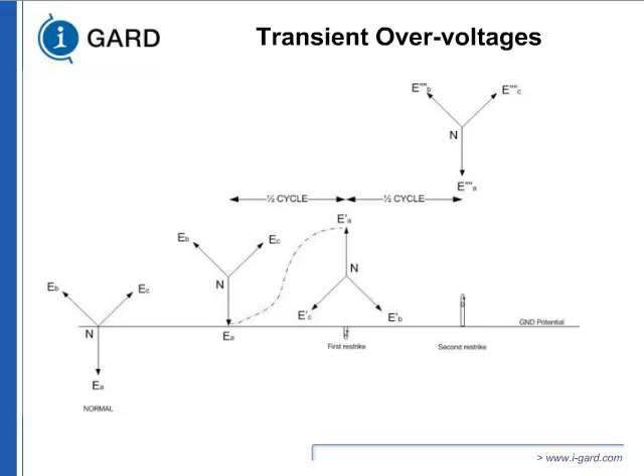If you have 480 volt switchgear on delta, you may have experienced the switchgear catching on fire because the current did not go to a level to trip the device, but the voltage was striking. We have measured on our sites almost 1200 volts or higher on a 480 volt system. It restrikes so much: transient overvoltage.